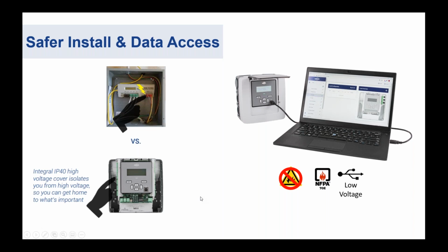Looking to the right, one simple thing that we did was move the USB to a place where you could get it without having to de-energize the panel. So if you had to add a load, add a configuration, or change something, and you wanted to plug into the front of the meter, you could do so without having to be in an arc flash suit and still be compliant with NFPA 70E. You can do this because there's double insulation between the high voltage inputs and the meter. We have the cover, which you can see in the lower left, and then we have the front cover and the display in multiple layers. It's been approved by UL, so we make sure we meet that double insulation requirement for those arc flash situations.